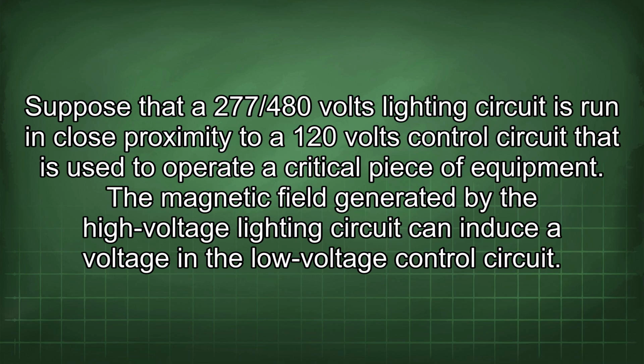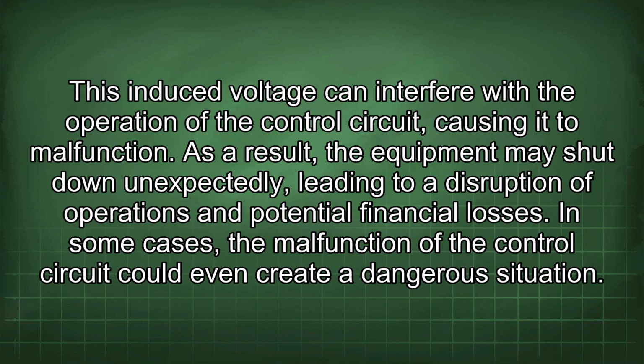The magnetic field generated by the high voltage lighting circuit can induce a voltage in the low voltage control circuit. This induced voltage can interfere with the operation of the control circuit, causing it to malfunction. As a result, the equipment may shut down unexpectedly, leading to a disruption of operations and potential financial losses. In some cases, the malfunction of the control circuit could even create a dangerous situation.